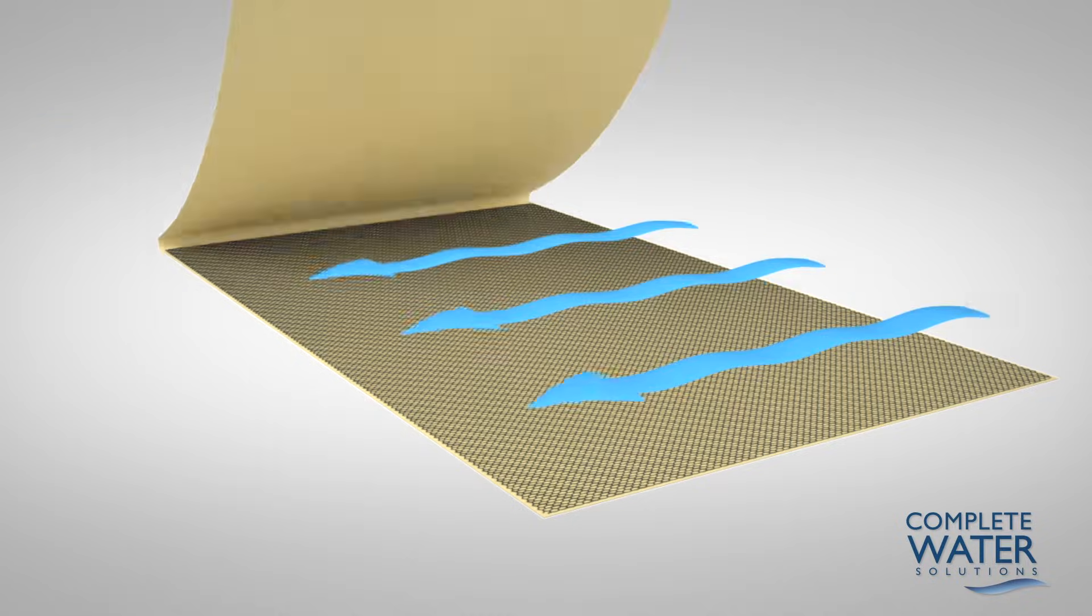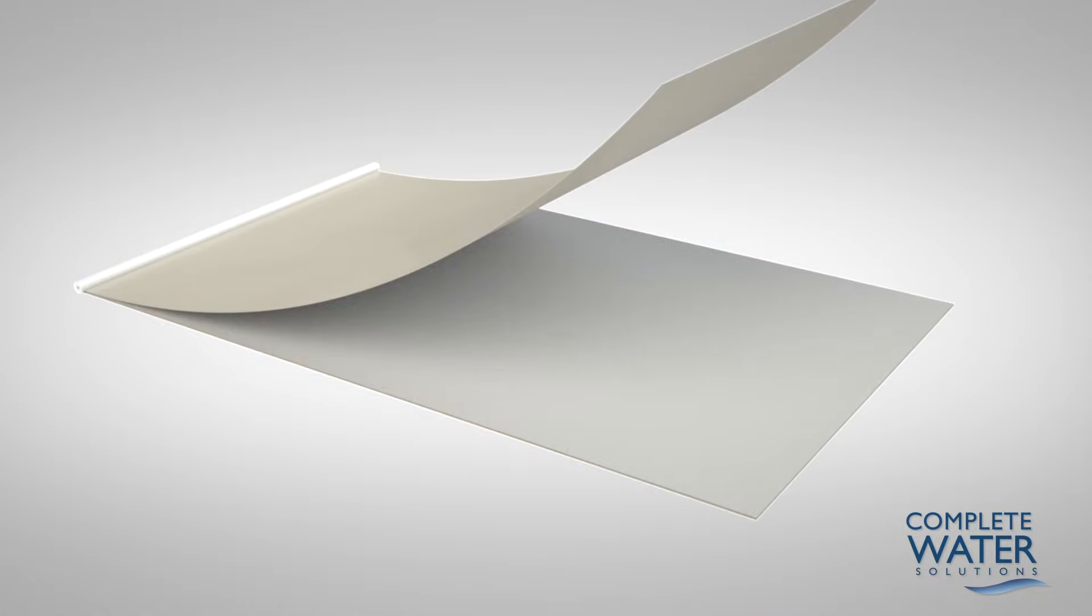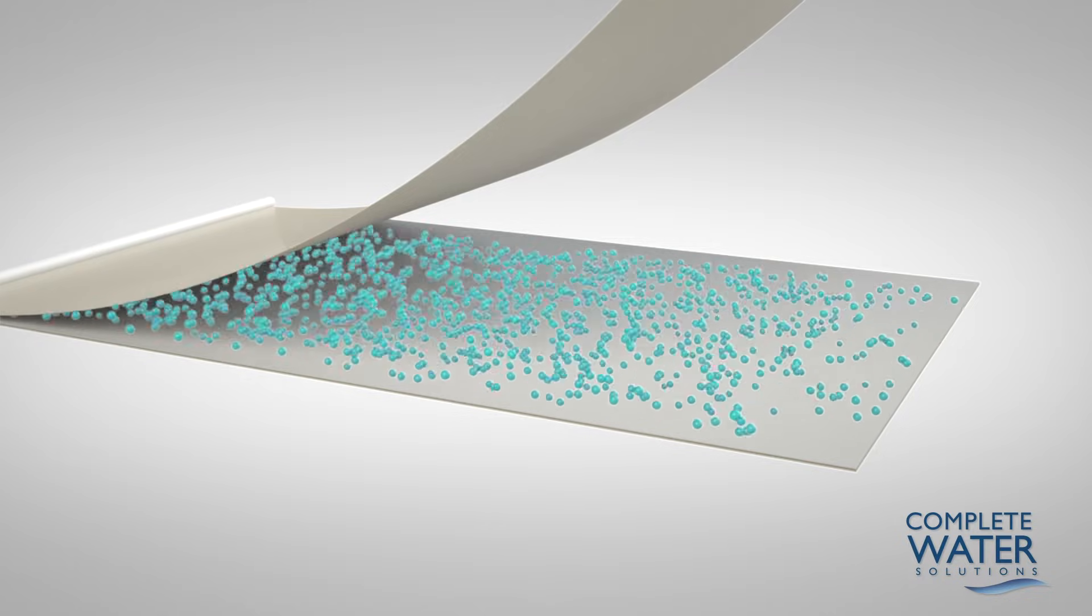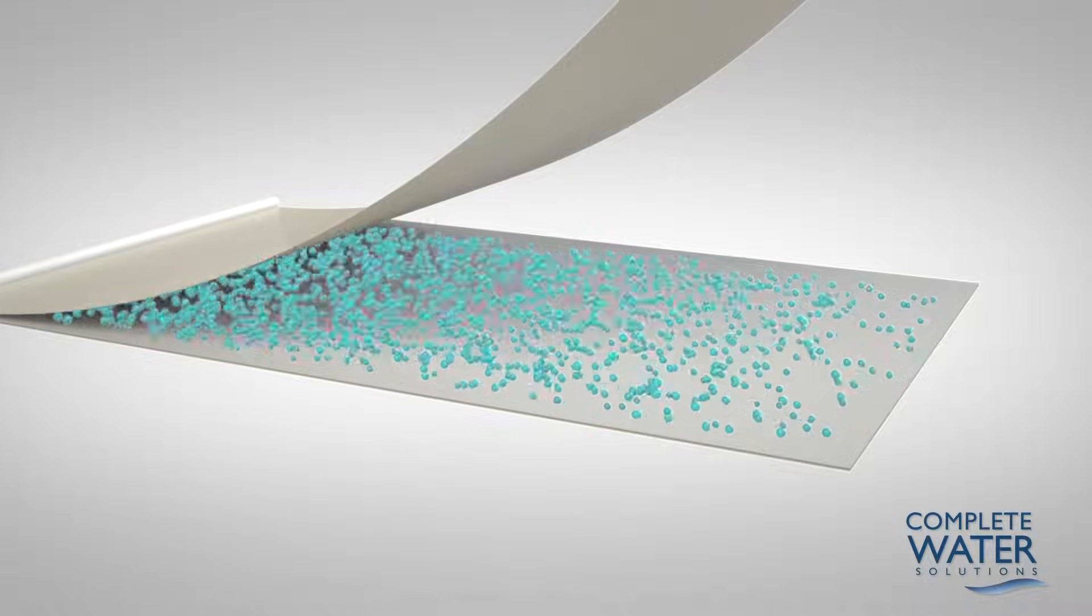This provides turbulence and creates space between the membrane sheets for the feed water. A sheet of permeate spacer is added to the membrane sheets and feed channel spacer. This enables the water product or permeate to flow evenly across the entire membrane surface even under high pressure.